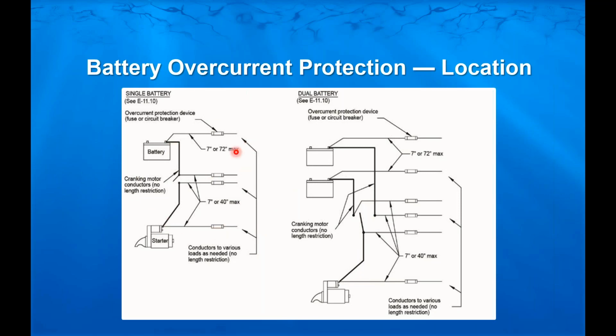So here's a diagram, a fairly simple system and a little bit more complex system with 2 batteries. Our main standard says we want that overcurrent protection within 7 inches of the source of power. In this case, we're dealing with a battery. So for wires connected directly to a battery, our exception is 72 inches. And that's the only place we get a 72-inch exception: at a battery, anything connected directly to a battery. So if we can't get that within 7 inches from the battery, we have up to 72 inches to get that overcurrent protection in. From any other source other than a battery, if we can't make 7 inches, we have 40 inches to get that overcurrent protection in. And you can see we've got 2 connections here to the battery, one from the unswitched side of the battery, one from the switch side of the battery, and even one coming off the starter post, which is not ideal, but I suppose it could be used as a source of power.